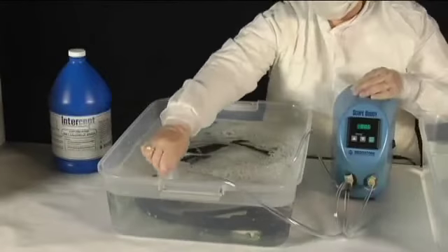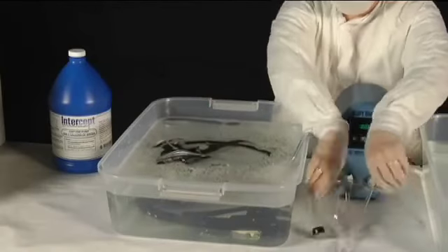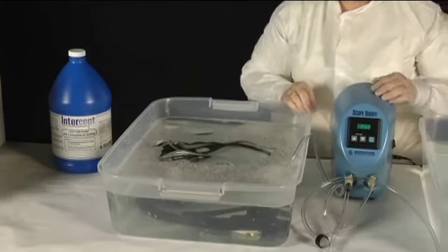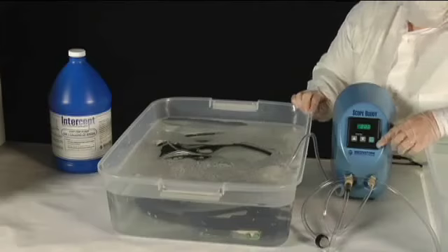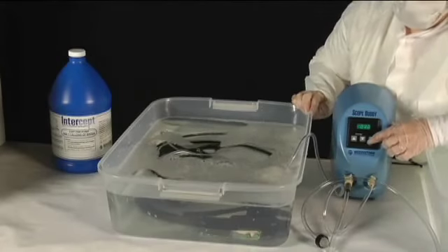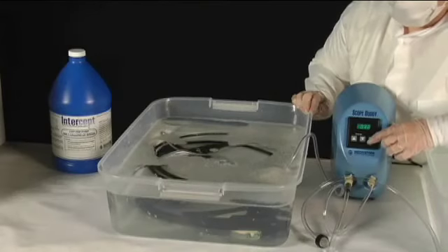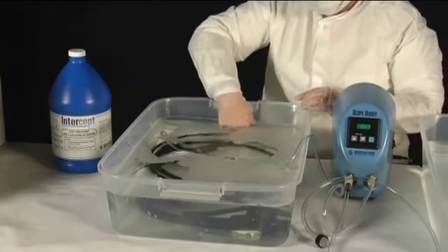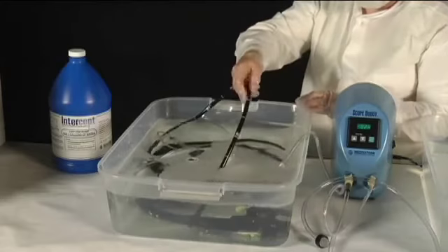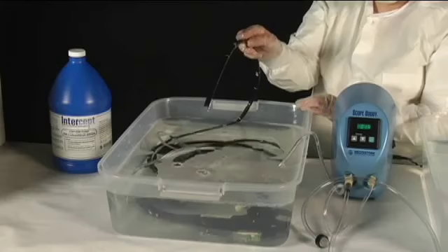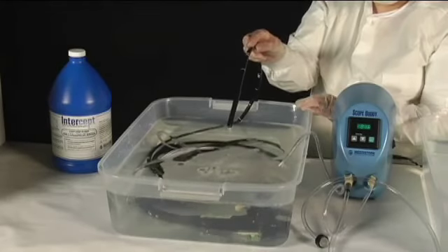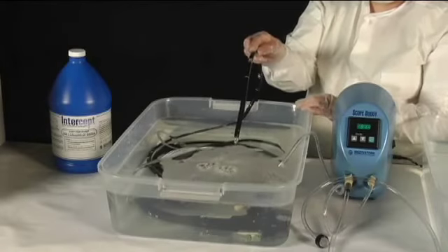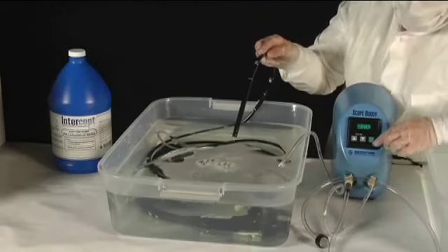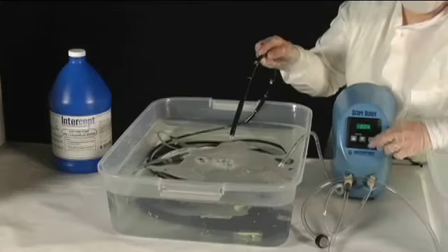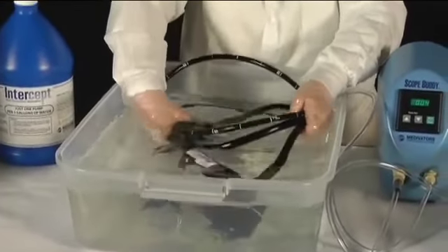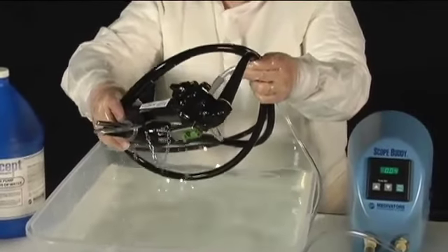After the timer counts down to 0, fluid flow will stop and an audible tone will be heard. To purge an endoscope of detergent, remove the fluid intake line out of the detergent solution and place on the counter. Press the Start-Stop button once to reset the timer to the original preset time amount. Press the Start-Stop button again to begin pumping air in order to purge the endoscope of the detergent solution. Press Start-Stop button to halt pumping when fluid no longer exits the endoscope. To rinse an endoscope with water, fully submerge the screened end of the fluid intake tube into the sink or clean supply container of rinse water.